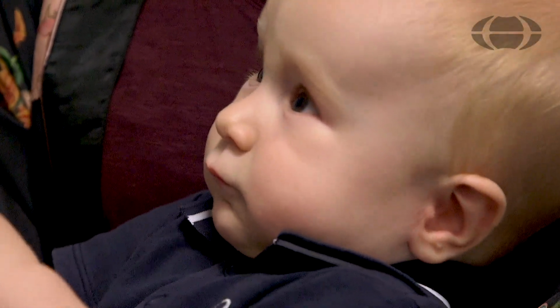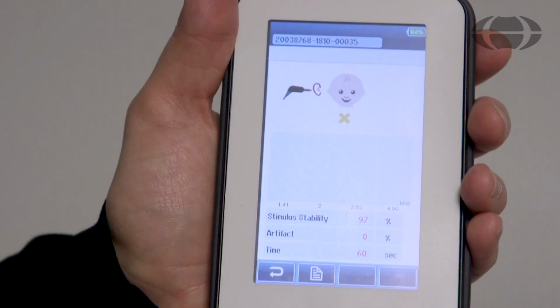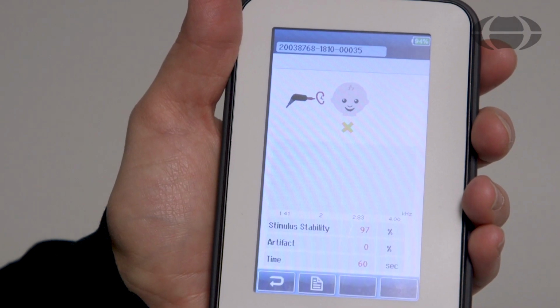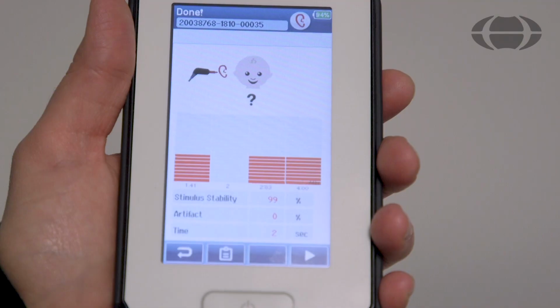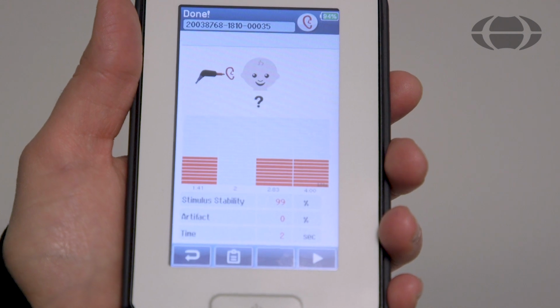When the test finishes, you will see either a green check mark, which indicates that the test has passed, a yellow cross, which indicates that the test has referred, or if you have manually stopped the test during the assessment, you will see a question mark, which indicates that the testing was incomplete.